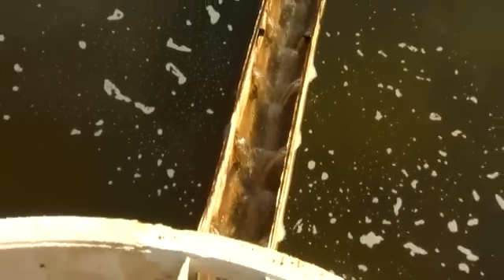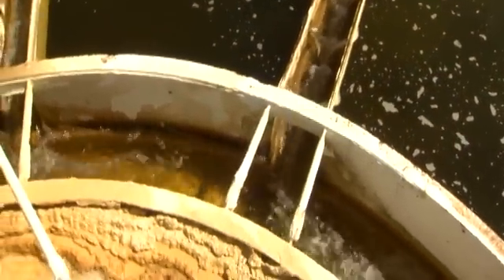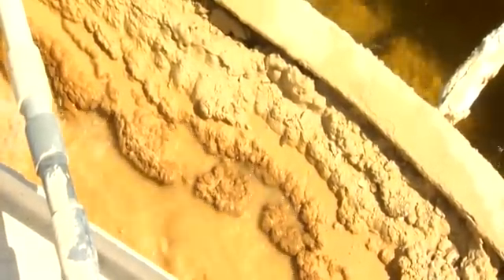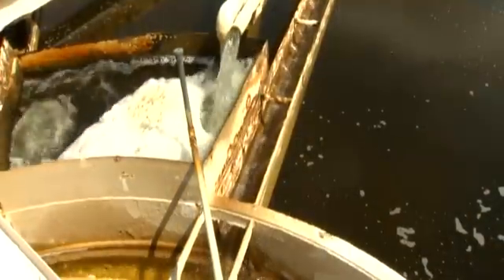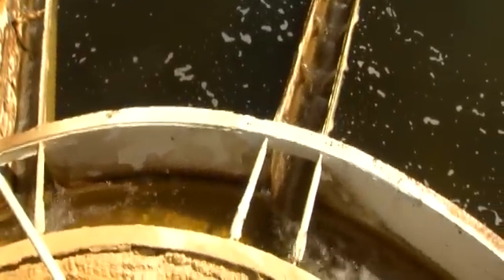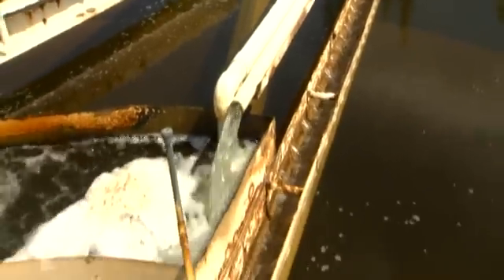The reactor is seen here. You see that yellowish milky looking water — that's the lime slurry mixed with the raw water. This water has some organics in it so the color tends to take on greater pigment, but lime mixed with water is generally going to be yellowish. You also note in the basin outside, the clarifier portion of the reactor, how clear that water is. That's because the lime softening reaction is a very fast reaction — it occurs within a matter of minutes.